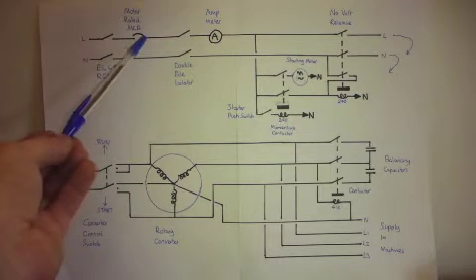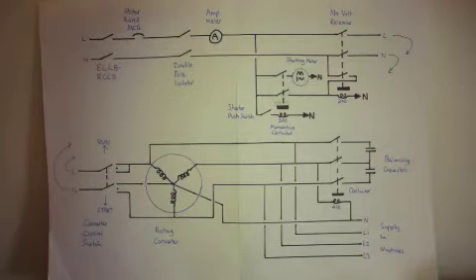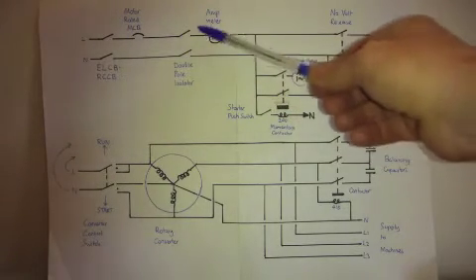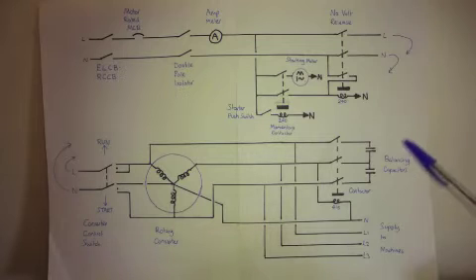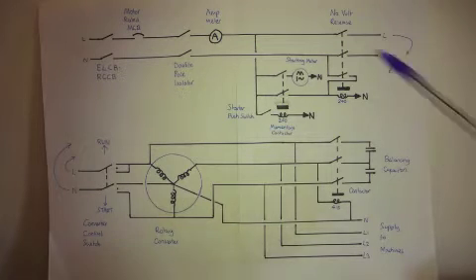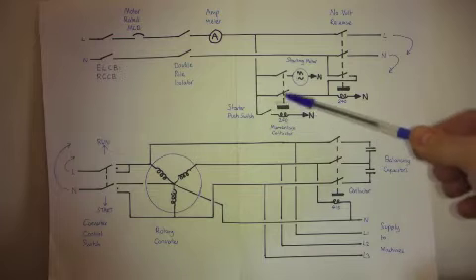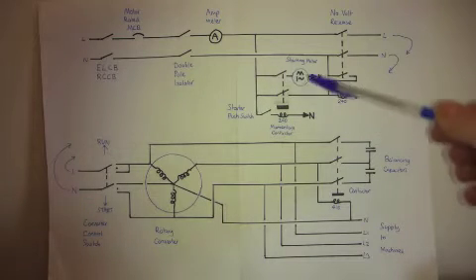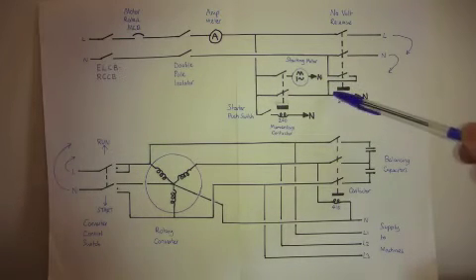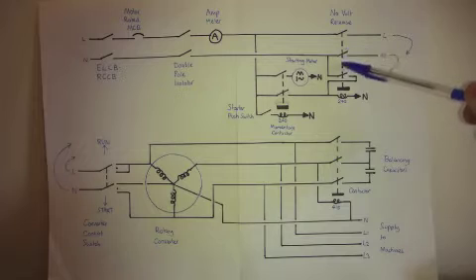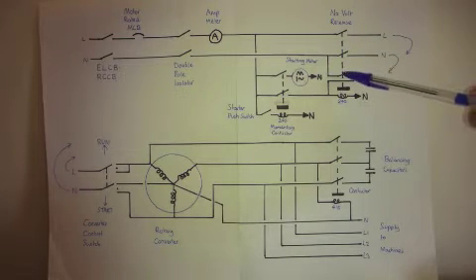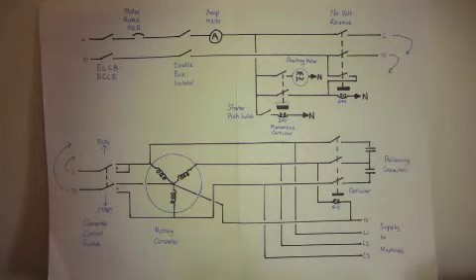The motor rated miniature circuit breaker in your consumer unit, double pole isolator, the amp meter showing the total current consumed by the converter. Here's the starter push switch, which operates the contactor to energize the starting motor and also pull in the no volt release, which then holds in once it's been switched on.